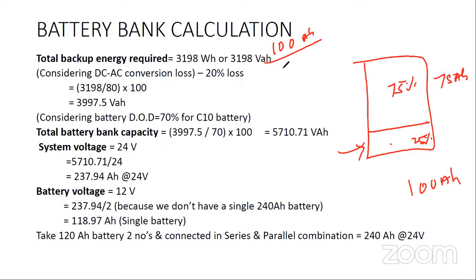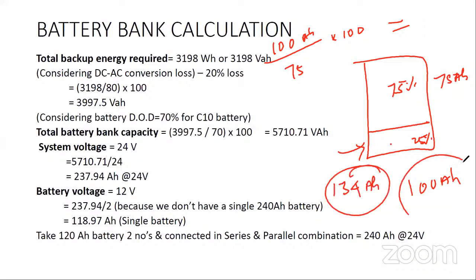Okay. So 100% is 75% into 100. That much power you should have, that much Ah you should have. So in this case, if you need 100 Ah of output, then if you divide 100 by 75 into 100, you probably need 134 Ah of battery in order to deliver 100 Ah of power to the load. You should not use a 100 Ah battery. So that is what the DOD is.